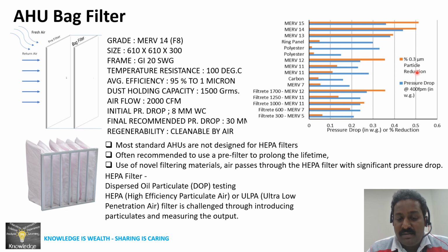In this, they will add some oil-based particles to challenge the HEPA filter, to see whether it can filter those or not. So that is called a DOP test, and each individual filter will be checked, to see whether it filtered those particles or not. So that is called a DOP test, dispersed oil particulate testing.